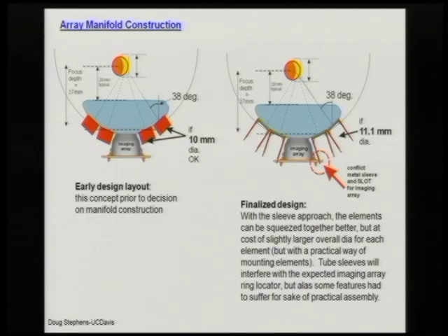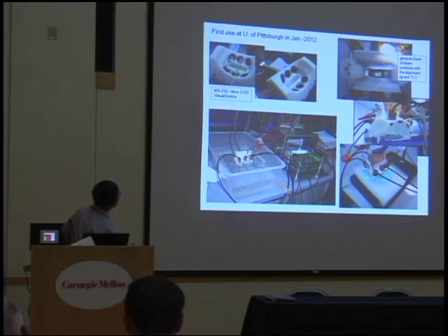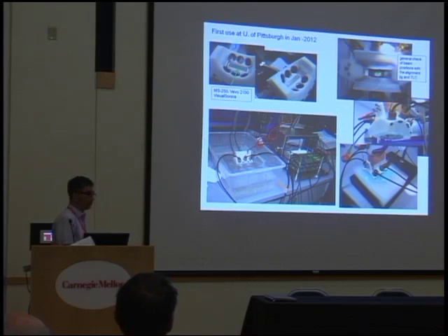So then we came to the optimal design in terms of frequency, imaging depth, and beam size to integrate into a commercial ultrasound transducer. This is the prototype, with a heating transducer integrated into a commercial system, the Vevo 2100, that you hit with this transducer and image, just to show the feasibility.